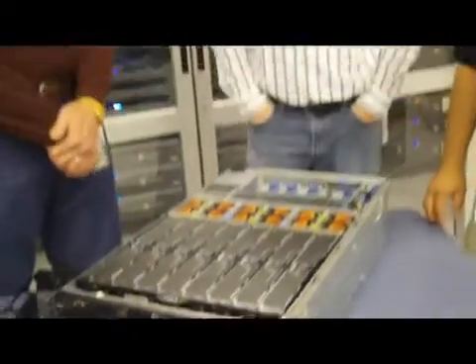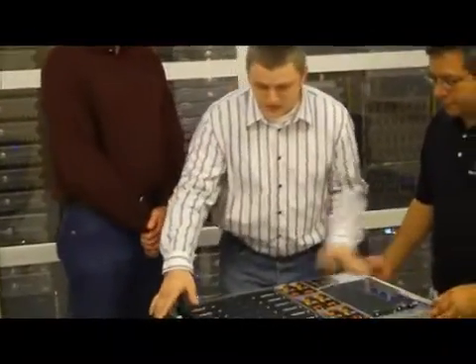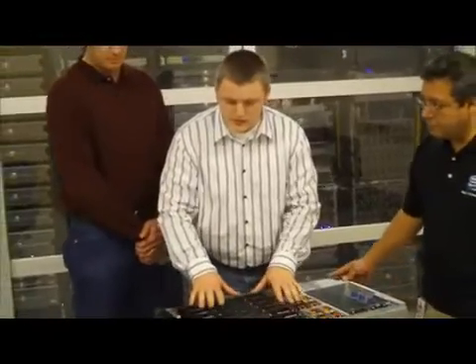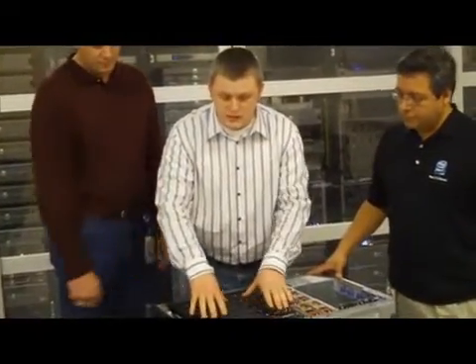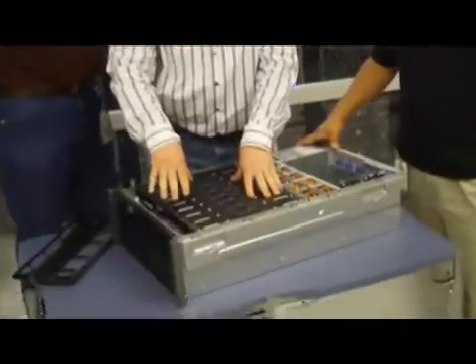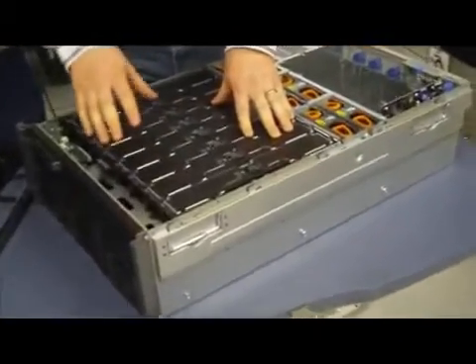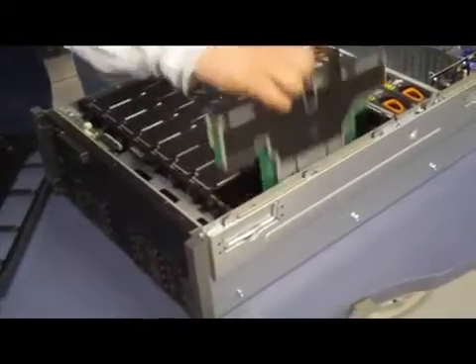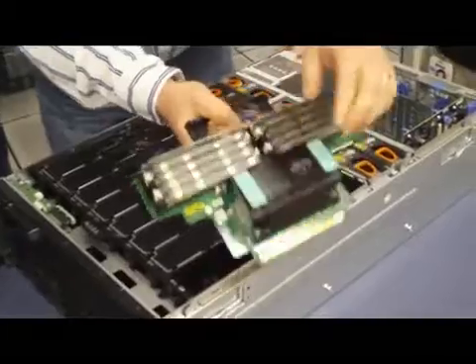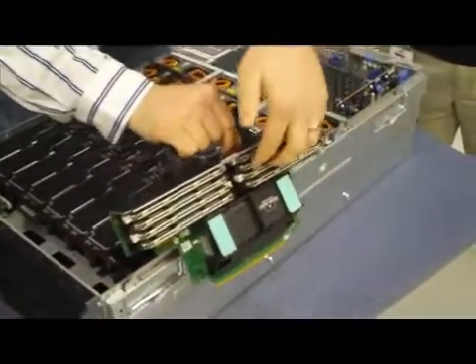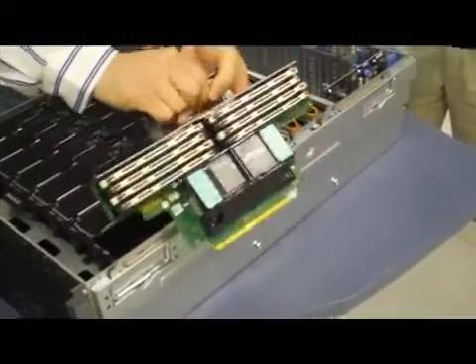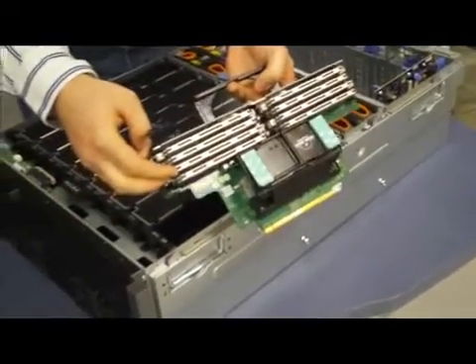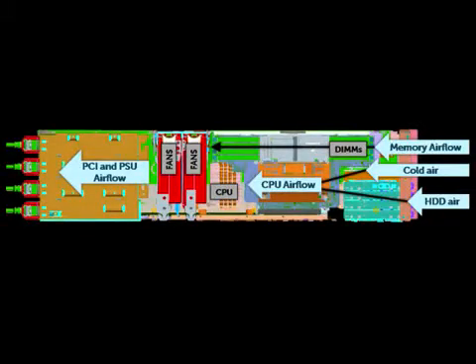Dominic will describe some of the thermal details. Looking at the architecture of the R910, component placement is really driven by thermal requirements. We need fresh air inlet to the memory and processors. Looking at the memory riser, the memory sits directly above the processors. This allows us to get fresh air into the memory and fresh air into the processors, to minimize the amount of airflow needed to cool these components.